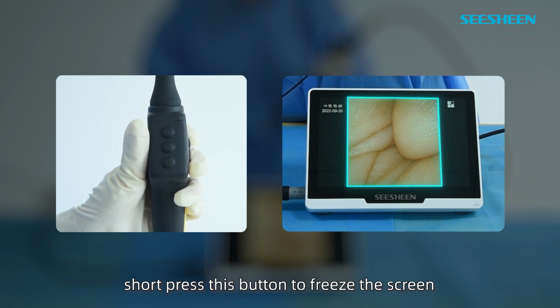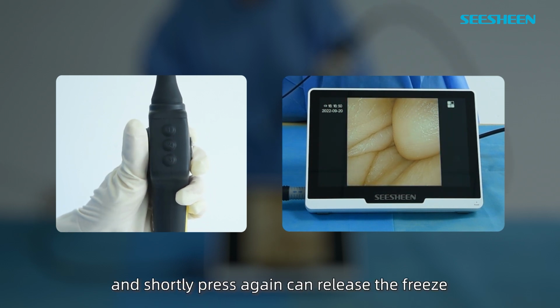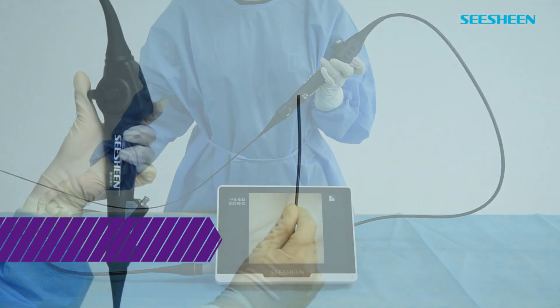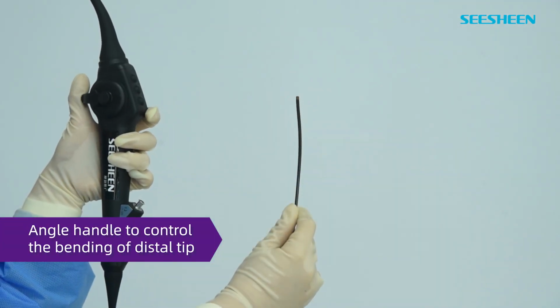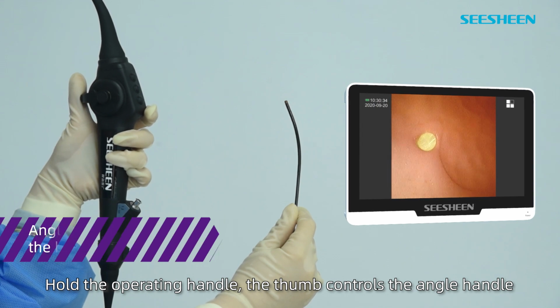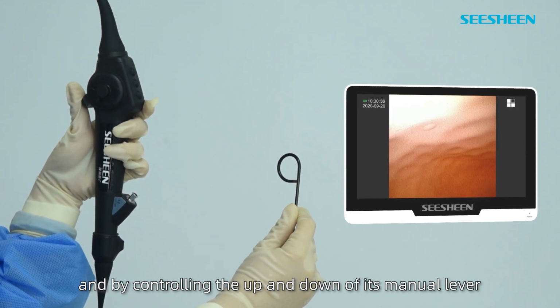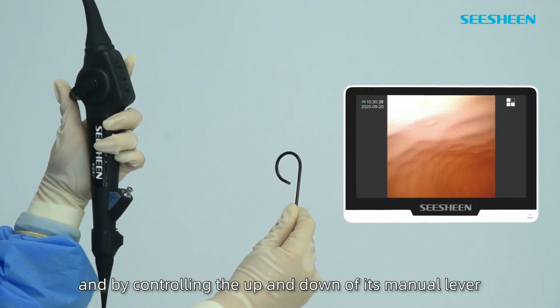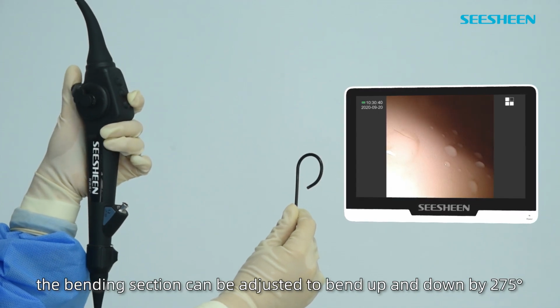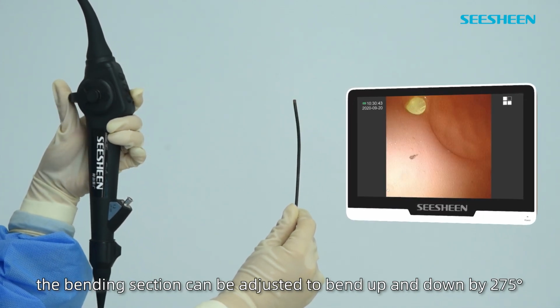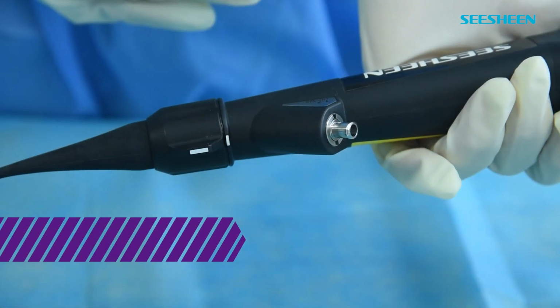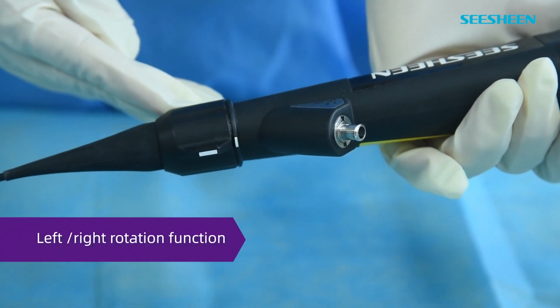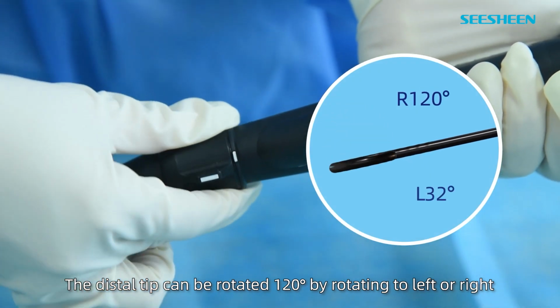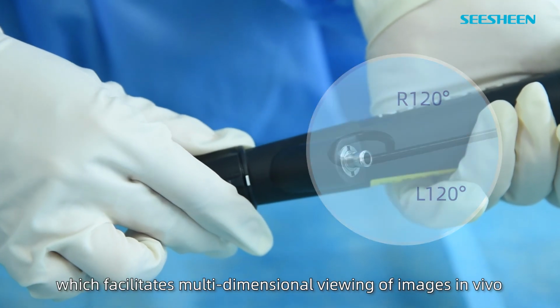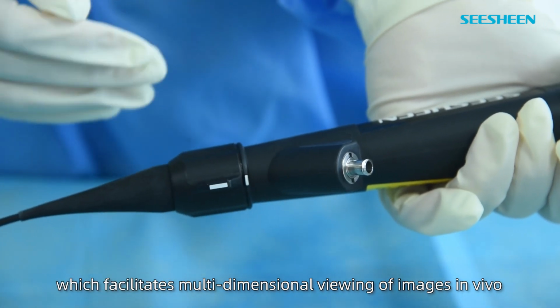Short press this button to freeze the screen, and shortly press again to release the freeze. Angle handle to control the bending of distal tip. Hold the operating handle, the thumb controls the angle handle, and by controlling the up and down of its manual lever, the bending section can be adjusted to bend up and down by 275 degrees. Left-right rotation function. The distal tip can be rotated 120 degrees by rotating to left or right, which facilitates multi-dimensional viewing of images in vivo.